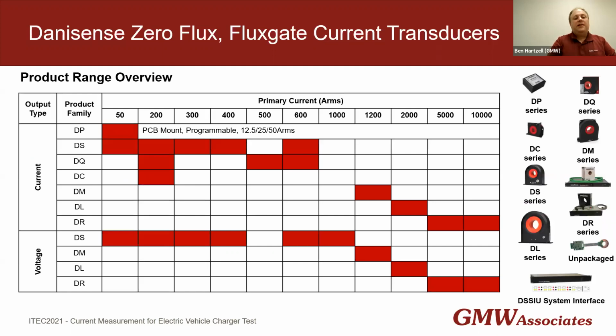Danisense current transducers come in a wide variety of ranges and packages. In terms of measurement range, we start as low as 12.5 amps full scale. This is for a programmable PCB mount version, the DP series, all the way up to over 10,000 amps for the DR series. Outputs can be either current or voltage. Again, that's just whether the burden resistor is built into the transducer head or you're taking the signal out as the secondary current directly.